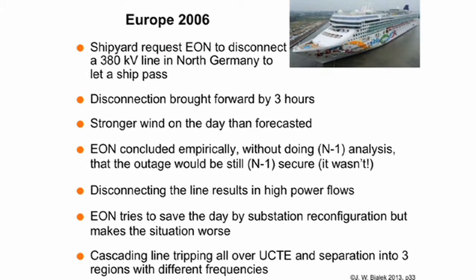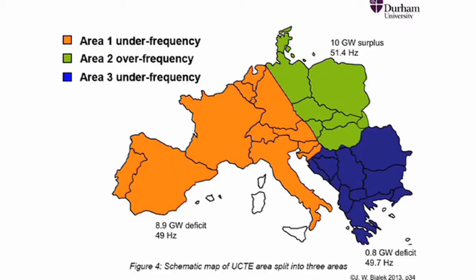The problem was that there were stronger winds on the day than forecasted. We are talking about northern Germany, a lot of wind generation. And E.ON, the local German utility, concluded empirically, without doing proper calculations, that the situation would still be n-1 secure. But it wasn't. So what happened? They disconnected the line, there were high power flows, and they tried to do something about it by so-called substation reconfiguration, but again they didn't do it properly and they made the situation worse. Because they made the situation worse, one line tripped, then the next line tripped, and so on, because it wasn't n-1 secure.